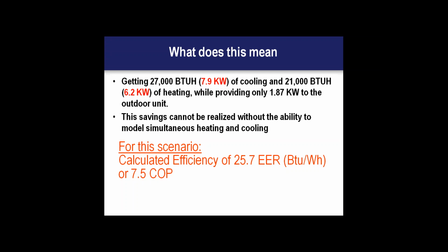And it's not uncommon to see this equipment cataloged and listed this way, especially if you look at the AHRI directory and start looking at ratings such as simultaneous cooling and heating efficiency, which is really just an effective EER when you're in that 50-50 balance point, that idealized balance point. So now, will you be at this every hour? Of course not, and that's going to depend heavily on your building and your application. And that's really where the need to have a tool that can accurately analyze these systems throughout the course of the year really becomes important.